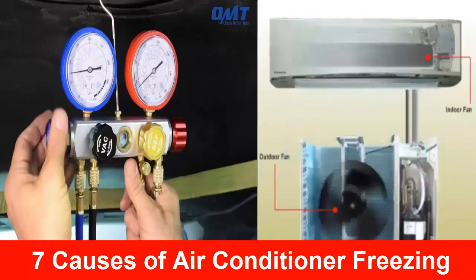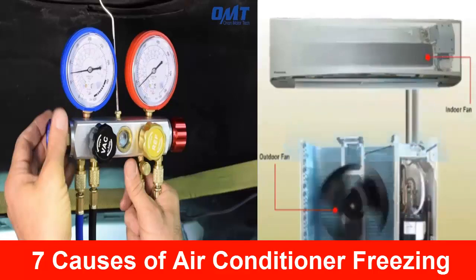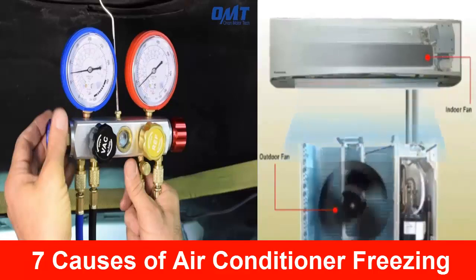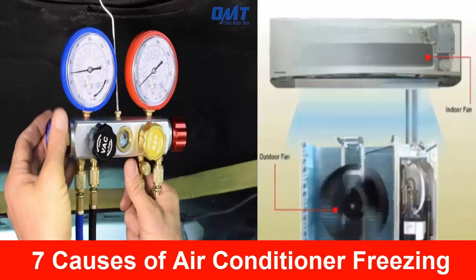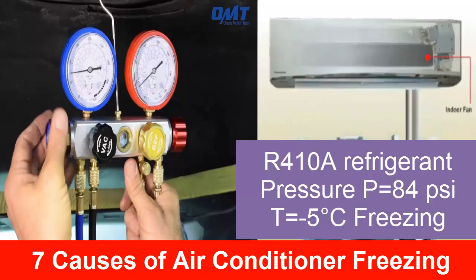7. Check the refrigerant pressure. If the pressure is low, it means that there is a lack of refrigerant. This can cause freezing, because the lack of gas lowers the pressure below normal, generating temperatures below zero.